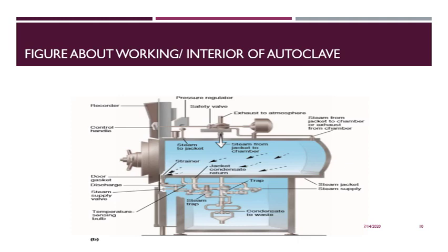At this temperature, saturated steam destroys all the vegetative cells and endospores in a small volume of liquid within 10 to 12 minutes. Treatment is continued for at least 15 minutes to provide a margin of safety. And of course, for larger containers of liquids such as flasks and carboys, much longer treatment times are required.